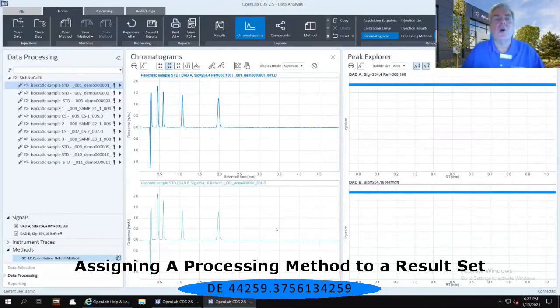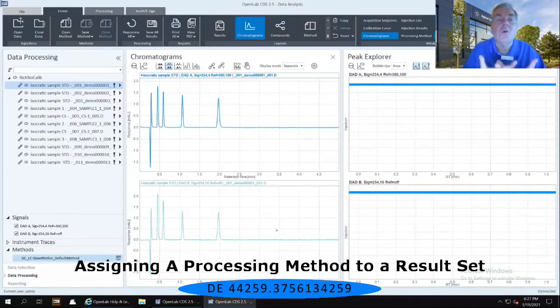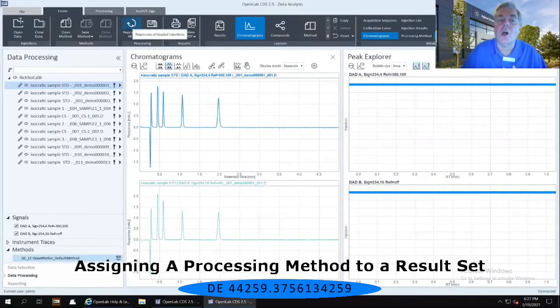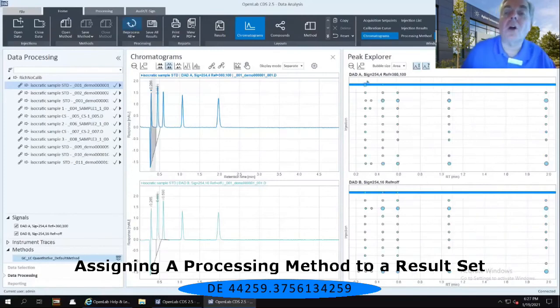So if I do want to have some integration that's done, then I have to reprocess that data with the method that I had just opened up. So in the upper ribbon, select the reprocess all icon, and that's now going to reprocess all of my injections for me.